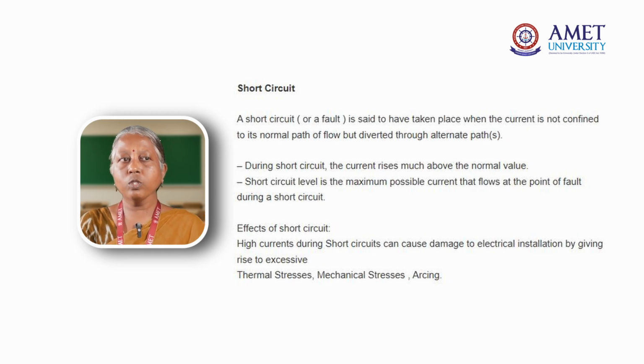So what are the effects of short circuit? Thermal stress, mechanical stress and arcing. When the temperature rises, there is a higher possibility of thermal stress. Due to thermal stress, you will get mechanical stress. When there is mechanical stress, there will be arcing in any electrical equipment onboard. To avoid this, we can go for lesser current and increased voltage. So these are the advantages: reduction in size, reduction in cost, ease of installation, less space, and less weight and size of the generator. These are the advantages of going for high voltage and reduction in current.